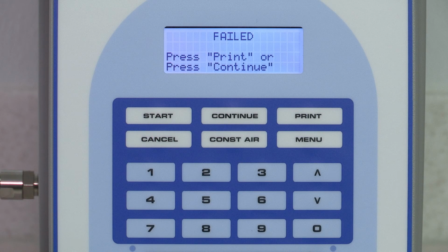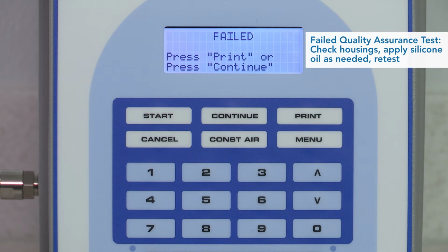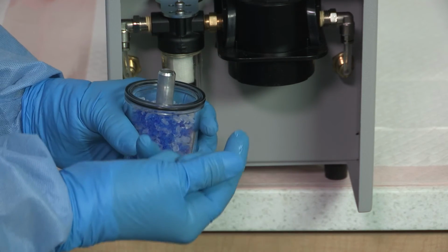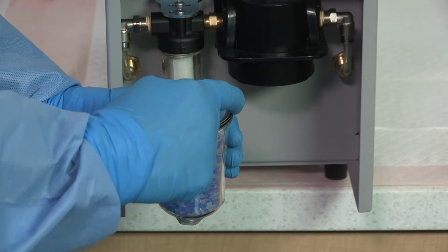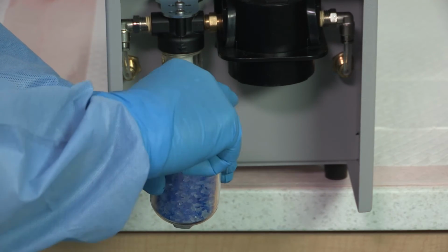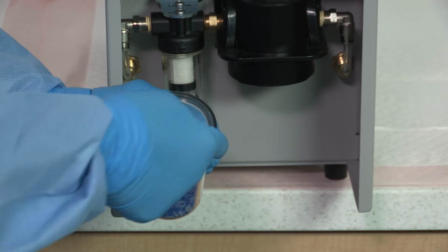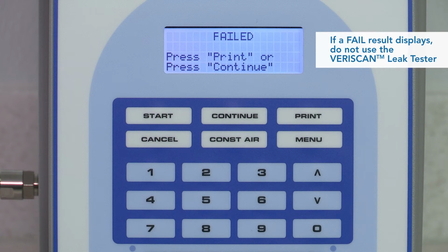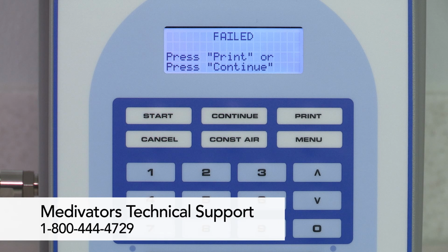If a fail result displays, then the daily QA test has failed. Check to ensure the drying crystal bulb and coalescent filter housing are tight. If the O-ring on the drying crystal bulb or coalescent filter housing is dry, use a gloved finger to apply a small amount of silicone oil. Rerun the QA test. If a fail result displays again, remove the unit from service. Never use the VERISCAN Leak Tester after a failed daily quality assurance test result. Contact Medivator's technical support at 1-800-444-4729 for further assistance.